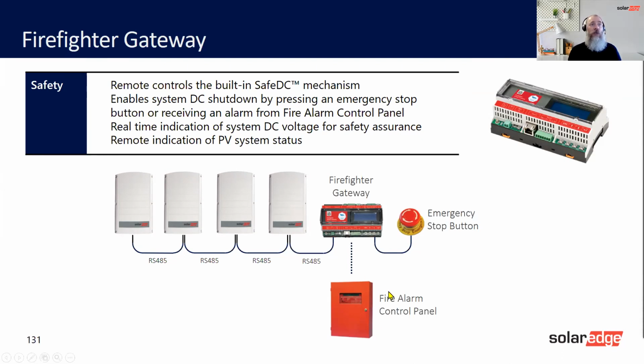The same way, if the fire alarm detects a fire, so your smoke detectors or heat detectors, what will happen is it will put a voltage on an auxiliary contact. This will then get the information. The contact will open or close, and then again it will communicate to the inverters, and all the inverters will shut down production and they will wait until this device is reset. So this is normally put in the reception. You would then press the emergency stop, or the fire alarm will go off, and all the inverters will shut down.